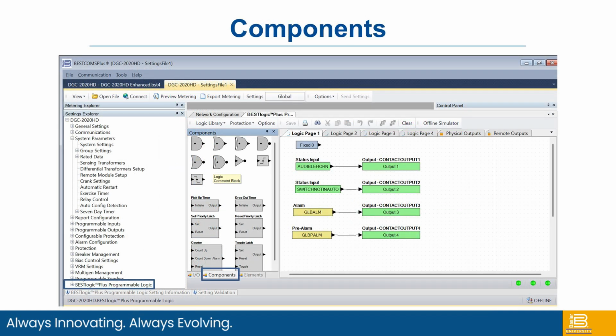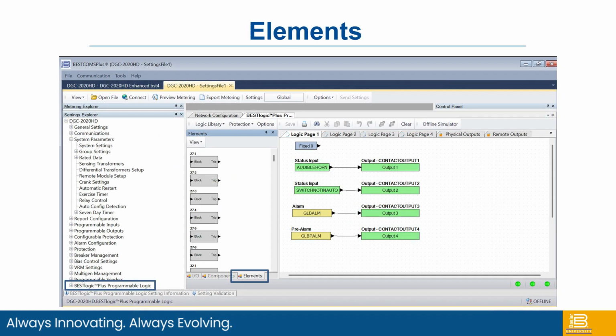Some of what we call components, so these are what we talked about, the ANDs and the ORs, etc. Elements are elements, so we call them elements because Basler's kind of focused a lot in the protection relay world, and that's typically what the relay world uses, same with ANSI. So all of the elements are under the ANSI names, like under voltage, over voltage, etc. There are also configurable elements, and then there's also elements that are functional things, like closing the generator circuit breaker. You go into this logic and whatever the input is, you're able to close the generator circuit breaker. Same thing with the utility circuit breaker and many other functions.